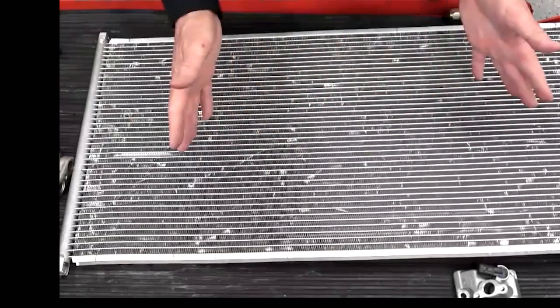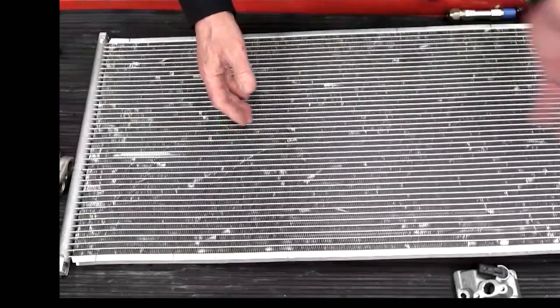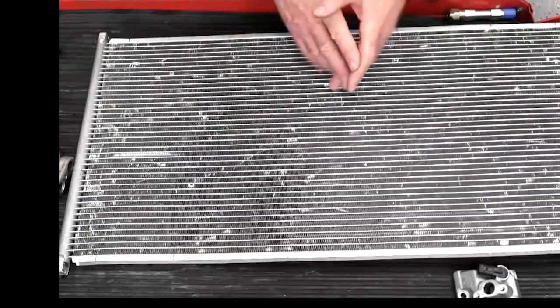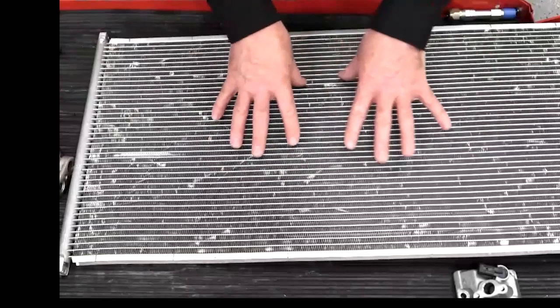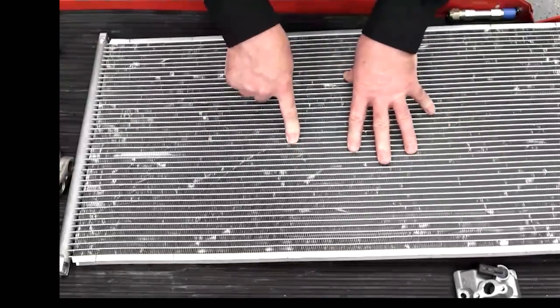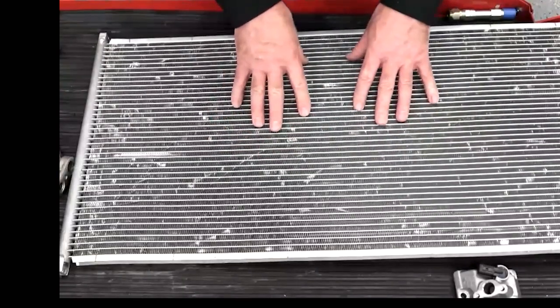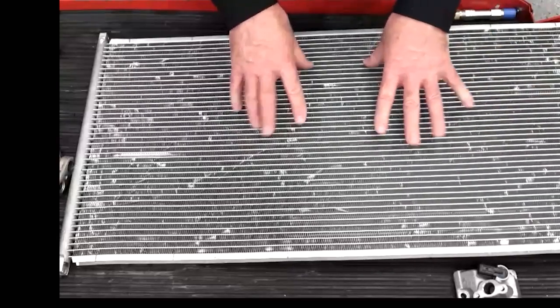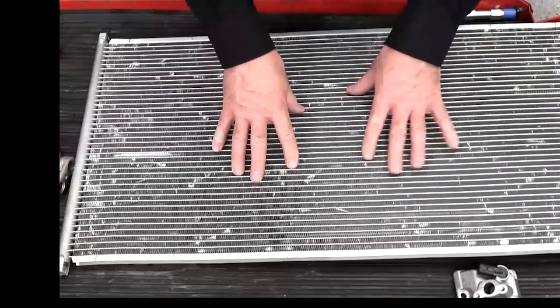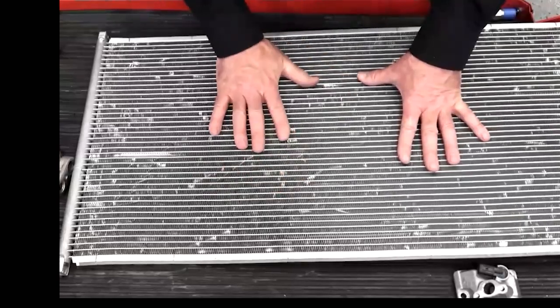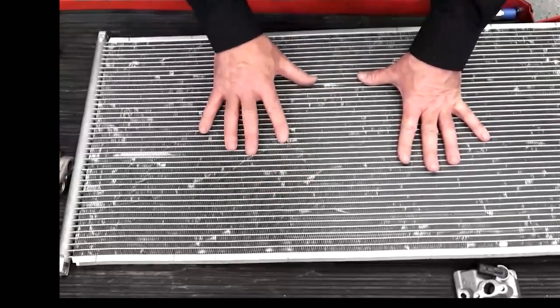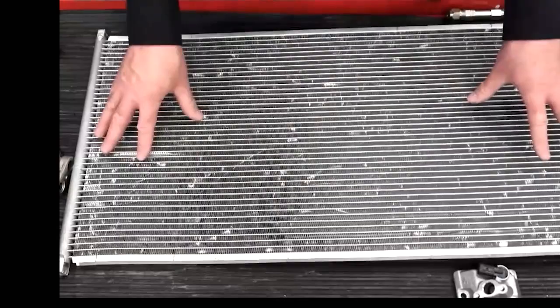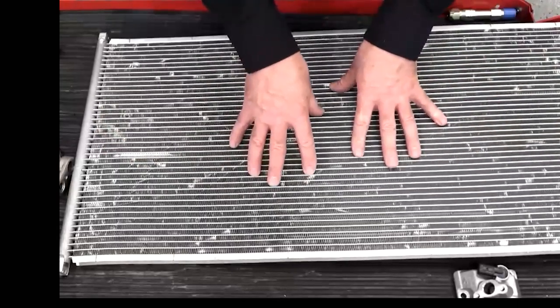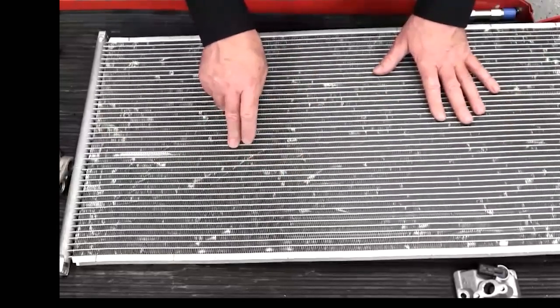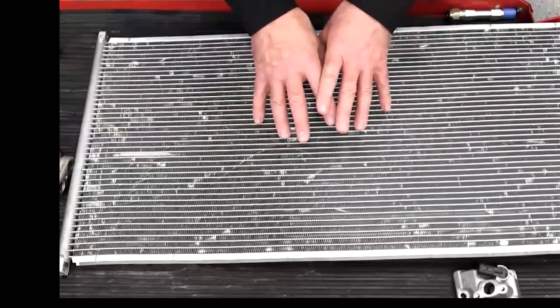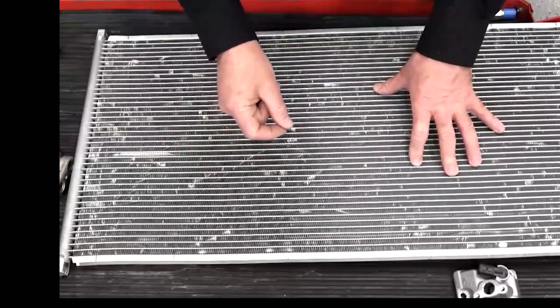And I have two other condensers. One is at, I think, 34 ounces, and the other one is at 42 ounces. So there's a lot of variation out there. The point I'm making is the factory charge on this Ford is 33 ounces. And if I take out the condenser I showed you first and install this condenser, this is a very flat tube multipath flow. It's a very efficient design. It's an excellent condenser.